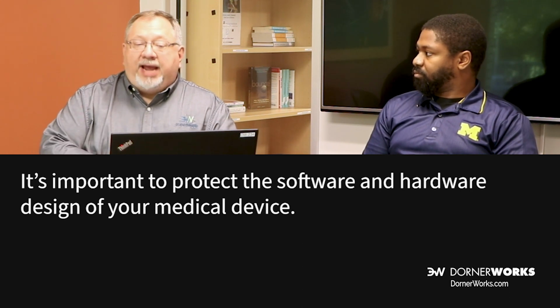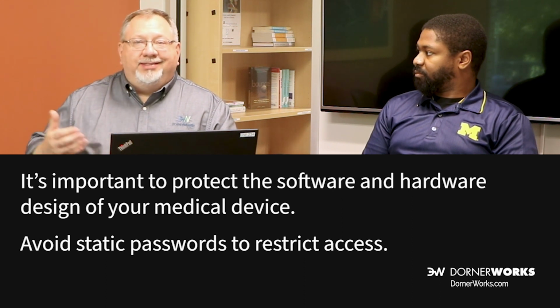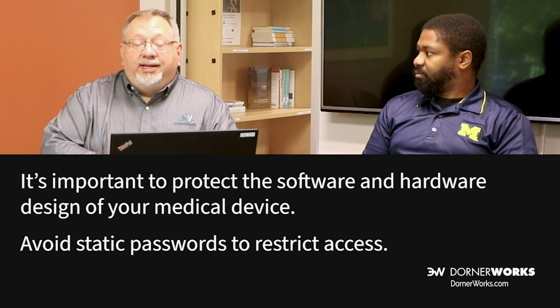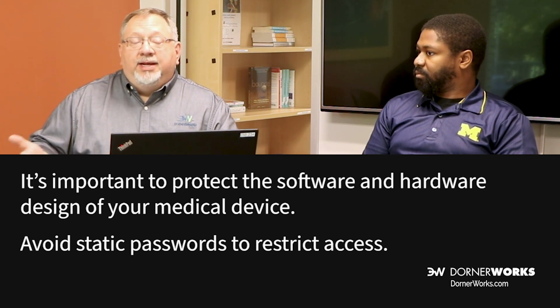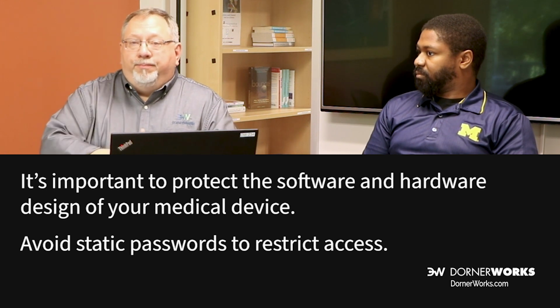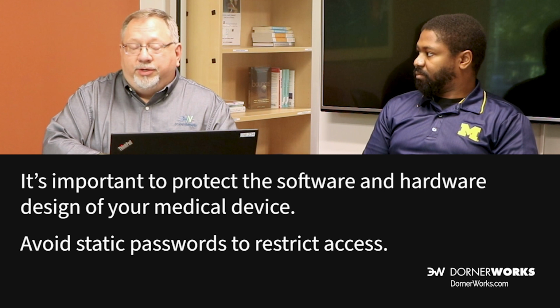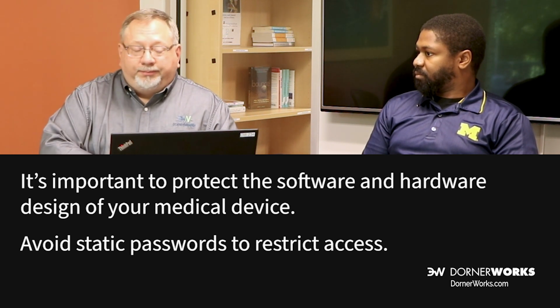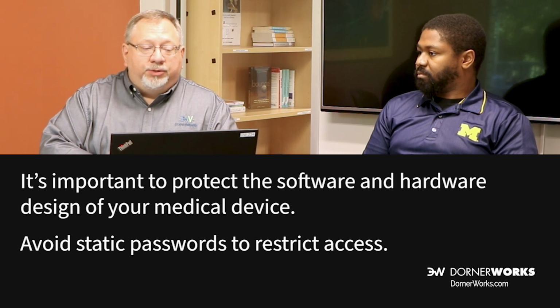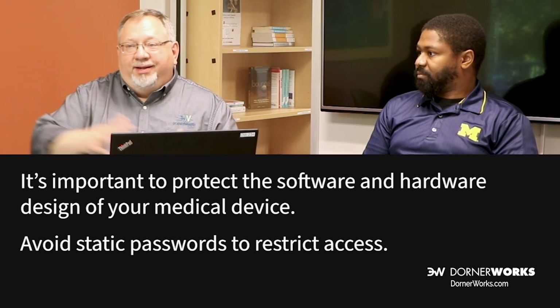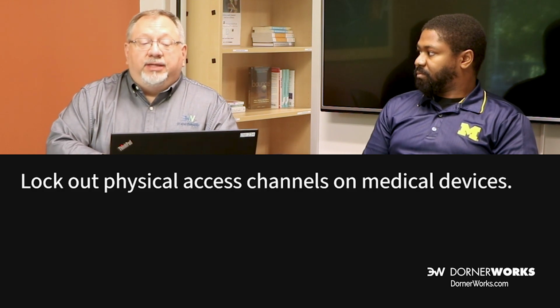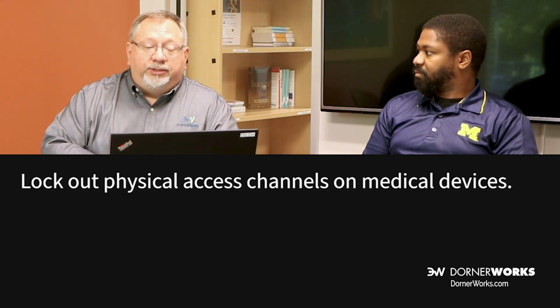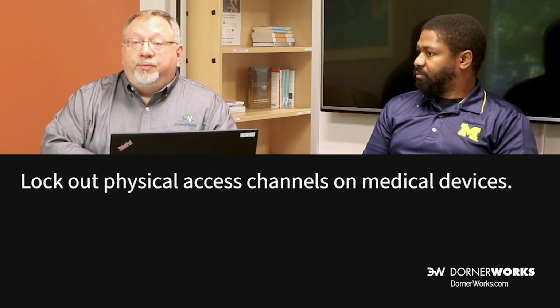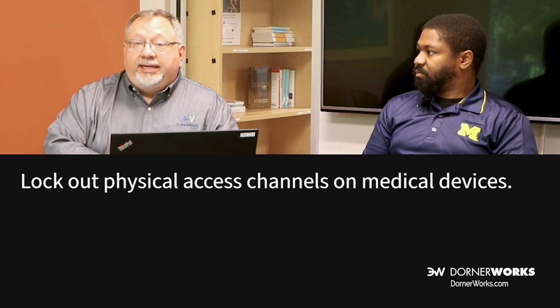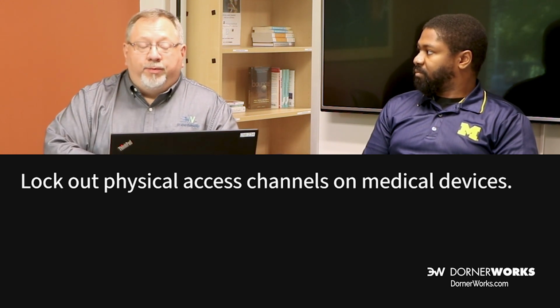Devices may have functionality that's password protected. Using a static password to access maintenance capabilities is a common way that medical devices are compromised. And then, if they had used a more secure password method or encryption method to authenticate the user, then that compromise would not have occurred. So no static passwords, because once you've leaked one, all of those devices are compromised. Medical device developers like DornerWorks need to lock out physical access channels, unused USB ports, SD card readers, and debug interfaces on the hardware. These are ways that somebody may get access to the device physically and compromise the device, gain access to your firmware.